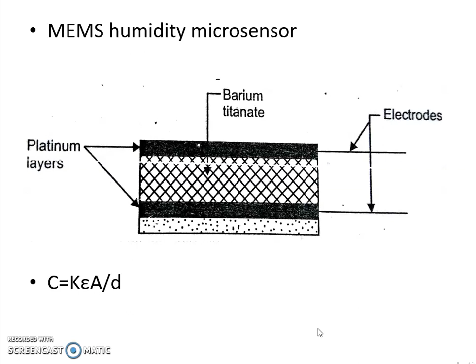Therefore, the capacitance of this capacitor depends upon the dielectric constant. When the humidity of the atmosphere changes, the dielectric constant of barium titanate also changes, so the capacitance of the capacitor also changes. Therefore the humidity can be measured in terms of change in the capacitance. This change in the capacitance is measured, which gives the value of humidity present in the atmosphere. It has the advantage that such systems have good mechanical and thermal stability, good frequency response and large voltage sensitivity. Because of these advantages, these MEMS humidity microsensors are very commonly used for the measurement of humidity.